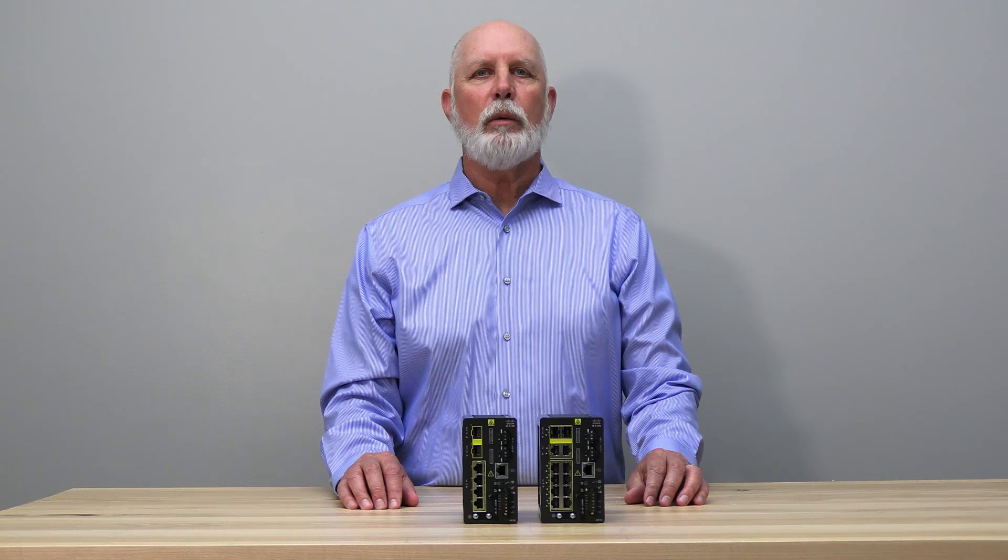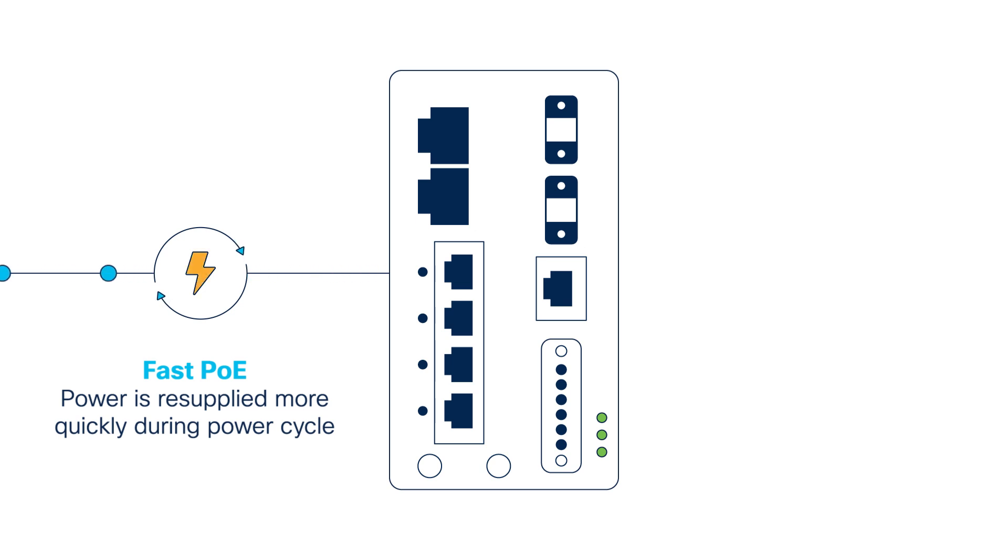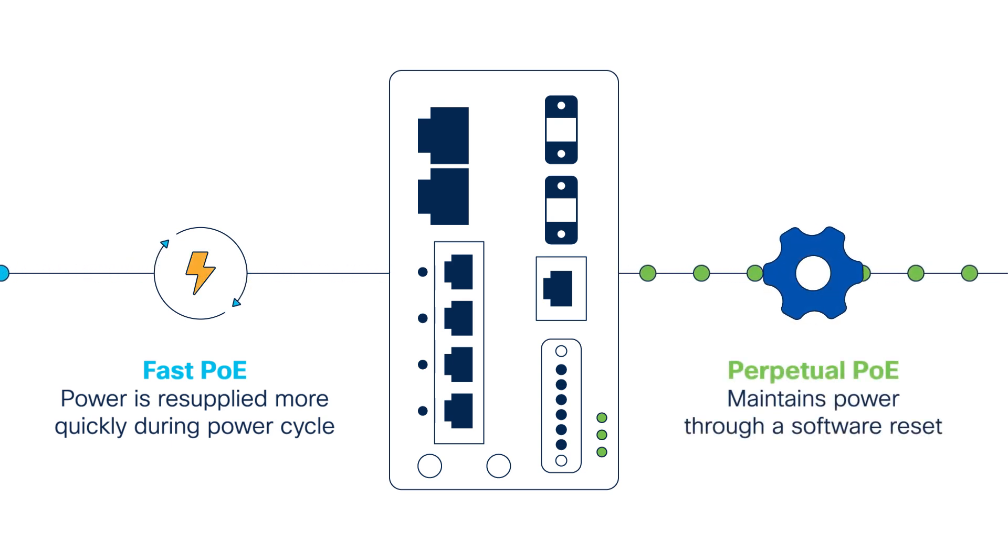Additionally, IE-3100 PoE models support fast PoE and perpetual PoE. Fast PoE is where PoE power is supplied sooner during an IE switch power cycle, allowing end devices to power up faster. Perpetual PoE maintains PoE power through a software reset of the unit, where PoE power does not stop flowing to the end devices from the 3100 during this reset.